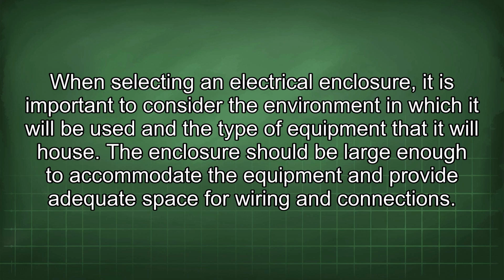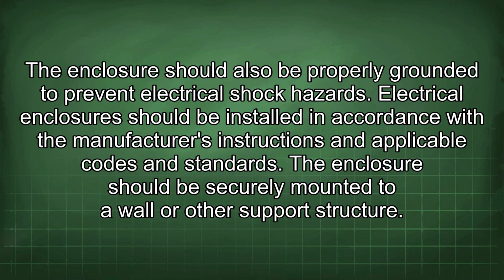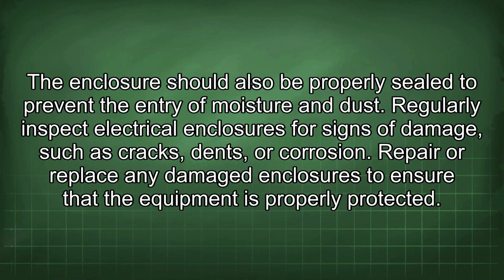The enclosure should be large enough to accommodate the equipment and provide adequate space for wiring and connections. The enclosure should also be properly grounded to prevent electrical shock hazards. Electrical enclosures should be installed in accordance with the manufacturer's instructions and applicable codes and standards. The enclosure should be securely mounted to a wall or other support structure. It should also be properly sealed to prevent the entry of moisture and dust.